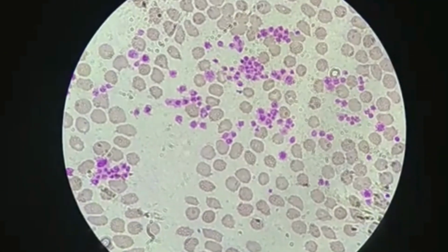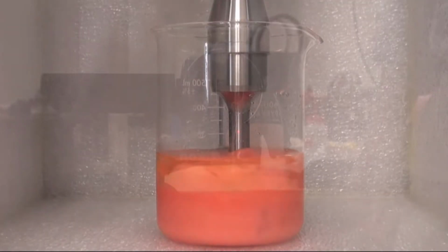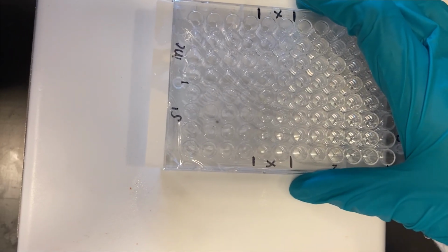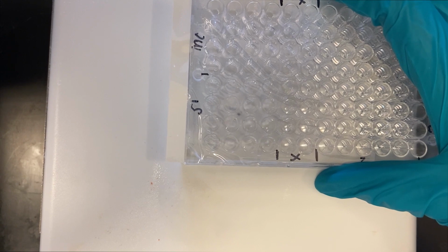Now, let's take a look at how we got to our final design. Platelet activation levels of 70% or greater indicate that platelets are fully activated. Techs in Slepian's lab usually use high-power machines to activate platelets for their testing. We wanted to downscale this to a 96 well plate in order to be able to test a large amount of biological compounds at once.